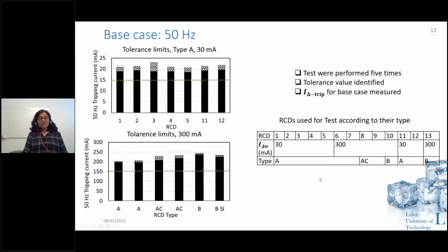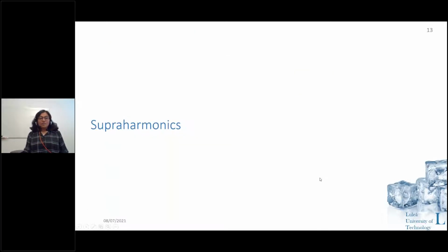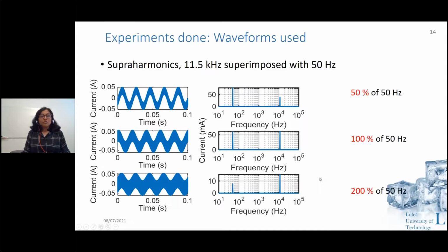So next, we have some results which I would present with supraharmonics. These are some of the waveforms that we used for supraharmonics. What we did is we made 3 test cases where a supraharmonic of 11.5 kilohertz is 50% of that of the fundamental, 100% of that of the fundamental, and 200% of that of the fundamental. And you can see the increase in the supraharmonics on the time domain waveform as well. On the right hand side is the frequency spectrum, where you can see the 50%, 100%, and 200% of supraharmonics.